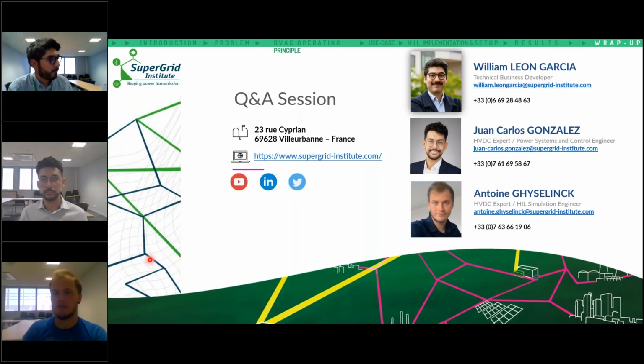Yeah, of course. I think these are topics that will grow with the needs of the market. For now, in our platform team, we would like to have more materials to test communication. For now, in our communication protocol, we have only a local area network via a switch, and we only do loss of packets and delay thanks to the simulation. The next step would be, for both of these topics, to have, for example, several switches, or one switch separated with VLAN, to have a more realistic communication network, to represent what will happen in MTDC grids. And we would also like to have materials, for example some switches that can emulate jitter, loss of packets, and delays. So that's for the communication part in the HIL.